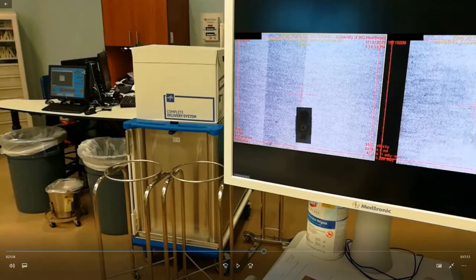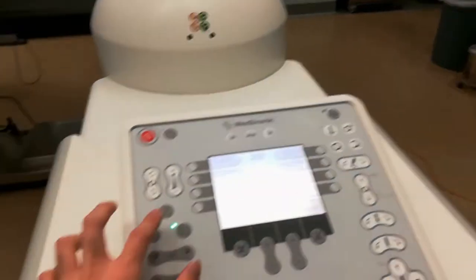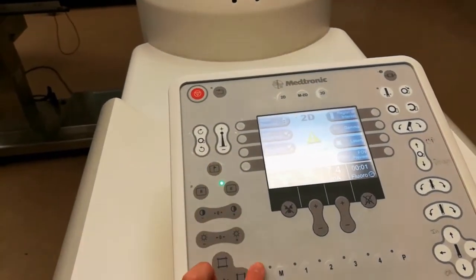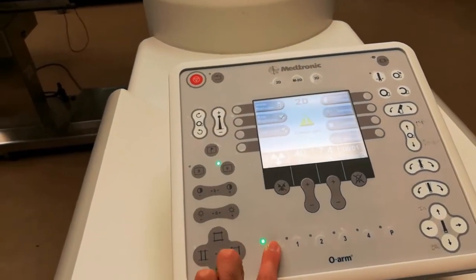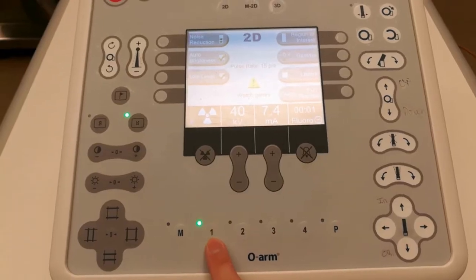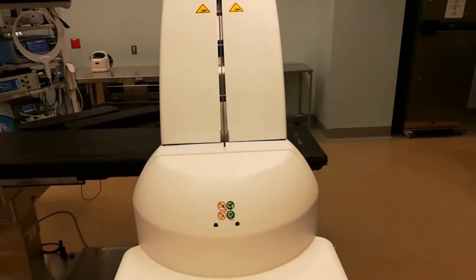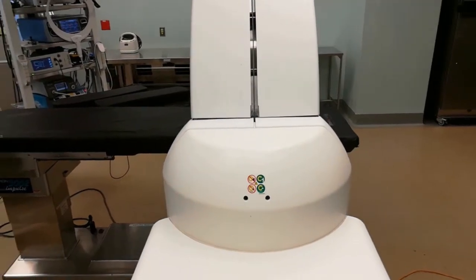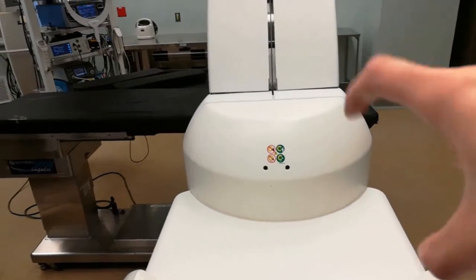Alright, so close enough, right? Whenever the surgeons are happy with where you're centering on these 2D scouts, they'll say, okay, that's good enough. You'll want to save the image and then hit M1. It memorizes the position of the gantry now, as in forwards, backwards, any tilt you have, and the exact rotation of the tube inside the gantry itself.